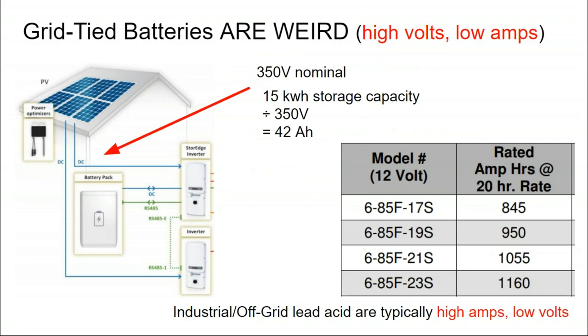You get into smaller gauge cable, that's the primary advantage. With lead acid batteries, your cables can become quite large—3-aught, 4-aught cables for residential off-grid battery banks. Anything larger than that starts not to become very feasible.